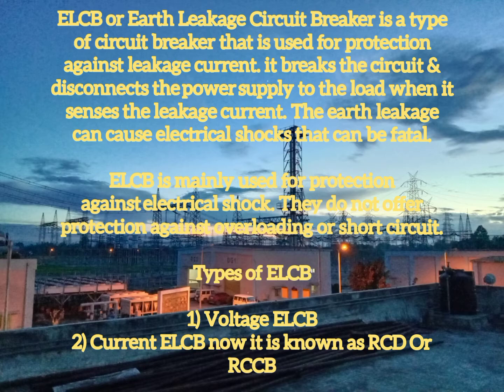ELCB is an earth leakage circuit breaker, and this type of circuit breaker is used for protection against a leakage current. It breaks the circuit and disconnects the power supply to the load when it senses the leakage current. So the leakage current can cause an electrical shock that can be fatal. ELCB is mainly used for protection against shock. It does not cover any over current or short circuiting of your circuits.